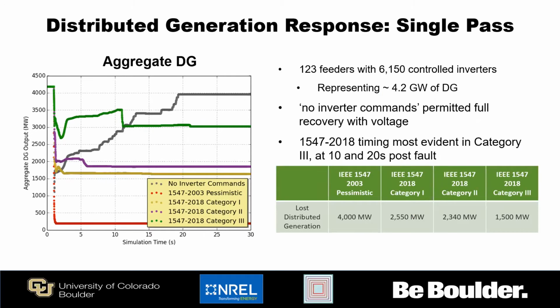If we do one of these single pass simulations, we can see varied responses from the aggregated distributed generation based on which IEEE standard is applied. Here on the left-hand side, you can see at the time of the fault, you experience this drop in DG output in all these cases. In the case of the 2003 pessimistic case, almost everything comes offline almost instantaneously. So this is a loss of 4 gigawatts of distributed generation at one time. Remember the peak load in this case is about 200 gigawatts, so that is a very significant drop in generation.